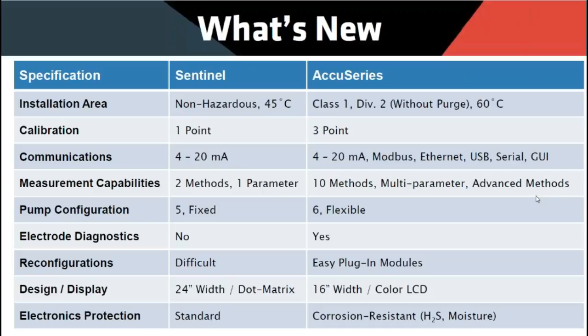Now, one of the most distinct differences from the Sentinel and AccuSeries is the Sentinel was very fixed to 1 or 2 methods, 1 or 2 parameters. You know, at most we could do a caustic and carbonate. Now we can do up to 10 methods, as well as multi-parameter and advanced methods. And so what I mean by that is the analyzer can store, let's say, an alkalinity and an acidity. So if you ever wanted to reconfigure it in the future, you would just select a different method, put the different titrant in, and be ready to go.